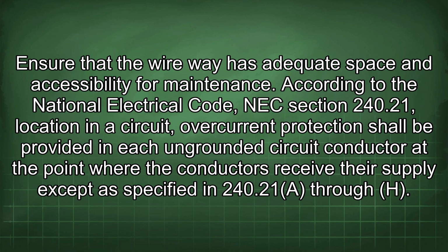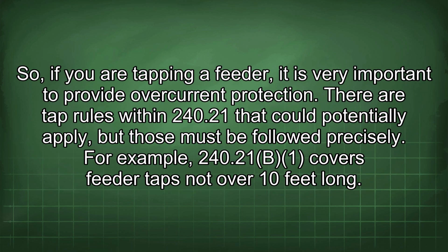According to the National Electrical Code, NEC Section 240.21, location in a circuit: overcurrent protection shall be provided in each ungrounded circuit conductor at the point where the conductors receive their supply, except as specified in 240.21(A) through (H). So, if you are tapping a feeder, it is very important to provide overcurrent protection.